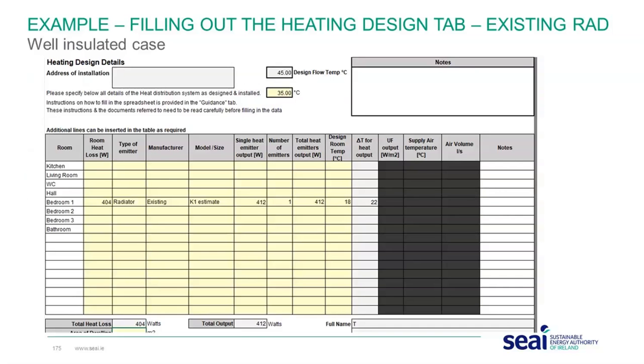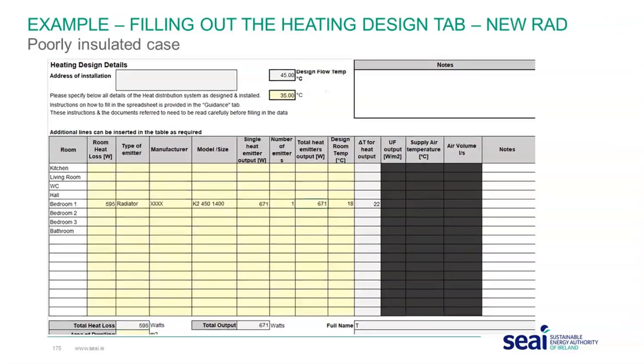So what do we do? Well, now we have this information, we can start filling in the heating design tab. So this one, the well-insulated case, we're putting in the existing radiator, we put in the room heat loss, and we put in the output of it. In the poorly insulated case, we've had to put in a new radiator because the existing radiator wasn't sufficient. So we put in the room heat loss, we put in the radiator, we'll ask you to put in the manufacturer details. We've anonymized it for this, we haven't put in the manufacturer details on it. And fill in the data sheet.